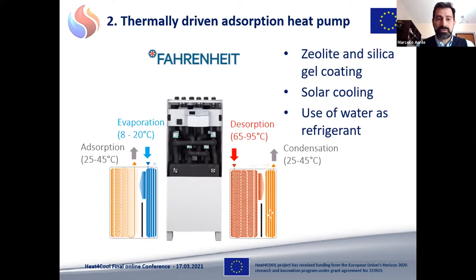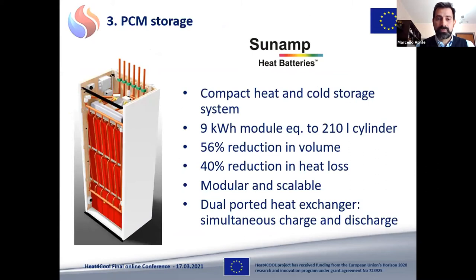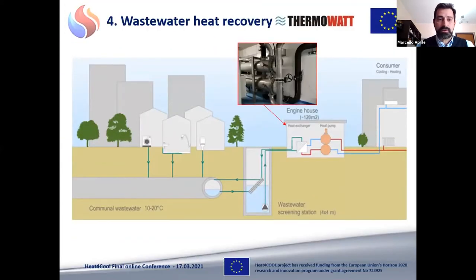And next, we see the phase change storage developed by SunAmp. Besides testing different phase change materials with different transition temperatures, SunAmp has developed a new compact unit, which is dual ported. That means that the loading and the unloading of the thermal energy can occur at the same time. And among the advantages of phase change storages with respect to the more conventional water one, we can surely mention compactness and modularity, which greatly enhance the possibility of installation in existing buildings, where space availability is of main concern.